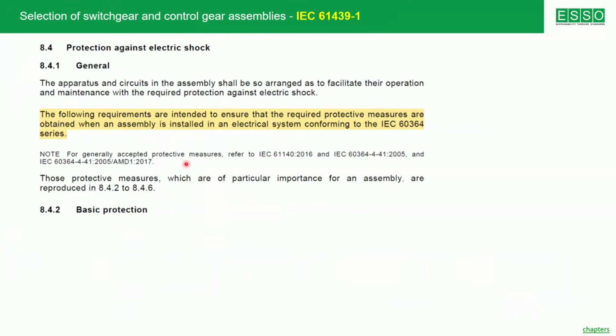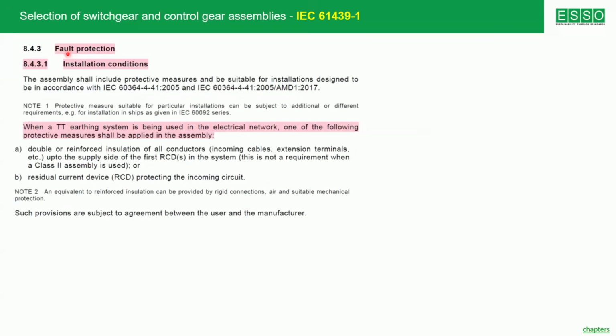Another subject which is again related to earthing is, for example, the panel boards, the distribution board. We call it switchgear and control gear assembly, and the respective standard is IEC 61439 Part 1. I'm just explaining the method of protection against electric shock. I have a slide which I will explain later. The following requirements are intended to ensure that the required protective measures are obtained when an assembly is installed in an electrical system conforming to the IEC 60364 series. The IEC 60364 series is nothing but our IS 732 or the National Electrical Code of India, which classifies safety into basic protection and fault protection. Earthing is a subject which is often for fault protection.